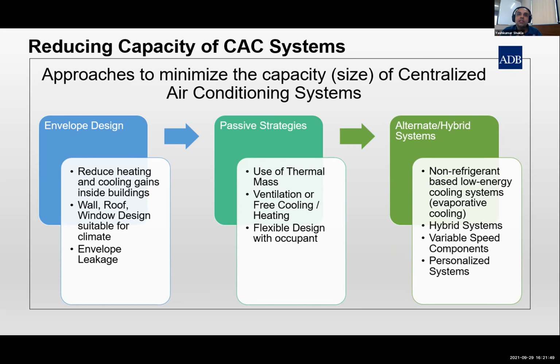This strategy again allows us to reduce the capacity of the air conditioning system. So that's the second step of trying to reduce the capacity of the CAC system. And finally, there will be extreme climate conditions where you will need a centralized air conditioning system. In these conditions, we first have to think about how we can use a non-refrigerant based, low energy cooling system in the building. For example, evaporative cooling in buildings.